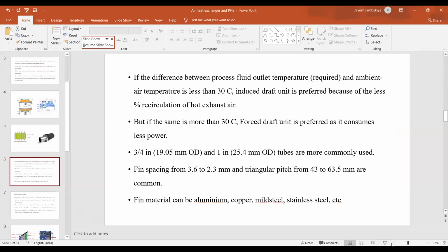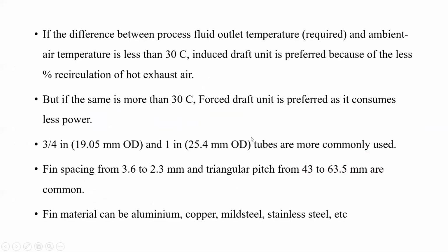Now, if the difference between process fluid out temperature, which is our requirement, and ambient air temperature is less than 30 degrees centigrade, the induced draft is preferred because of less recirculation of hot exit air. We know that air becomes hot because it is used to cool the process fluid, so its temperature will definitely increase.